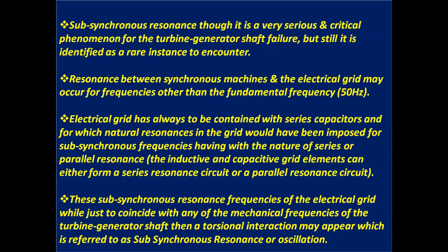Subsynchronous resonance, though it is a very serious and critical phenomenon for turbine generator shaft failure, is still identified as a rare instance to encounter. Resonance between synchronous machines and the electrical grid may occur for frequencies other than the fundamental frequency, that is 50 Hz. The electrical grid has always to be contained with series capacitors, for which natural resonances in the grid would have been imposed for subsynchronous frequencies, having the nature of series or parallel resonance.